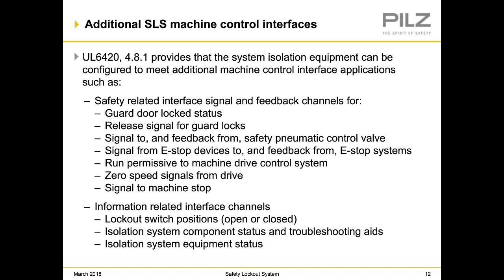UL6420 provides that the system isolation equipment can also be configured to meet additional machine control interface applications, such as guard door lock status, release signal for guard door locks, the signal to and feedback from safety pneumatic control valves, signal from e-stop devices and feedback from e-stop systems, the run permissive to a machine drive control system, zero speed signals from a drive or another type of zero speed monitoring, signal to the machine stop. Also, information related interface channels can include lockout switch positions, whether they're open or closed, isolation system component status and troubleshooting aids, and isolation system equipment status.